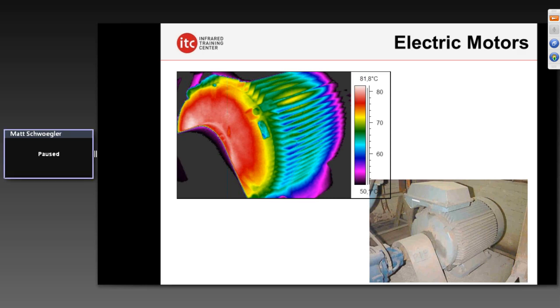We can look at electric motors — the overall temperature to see if it's exceeded its insulation rating, the motor bearing to see if it's heating up and needs a shot of grease, or the motor junction box to get an indication of a connection problem inside. A motor bearing could be warm for several reasons: over-lubricated, under-lubricated, a bad bearing, or a misalignment issue. But infrared gives us that data point — a heads-up that something is happening and we need to investigate more closely.